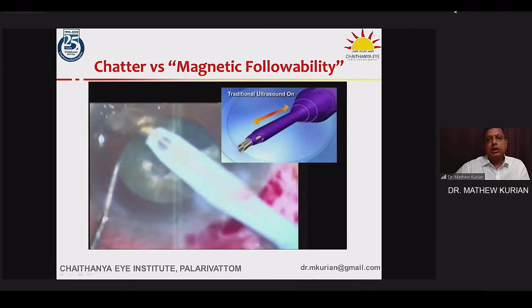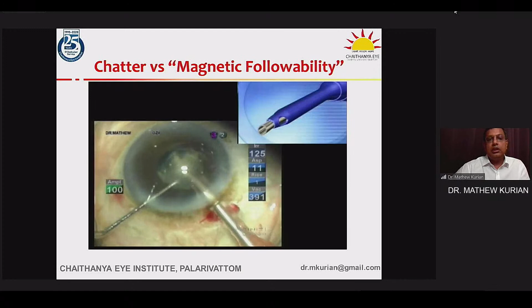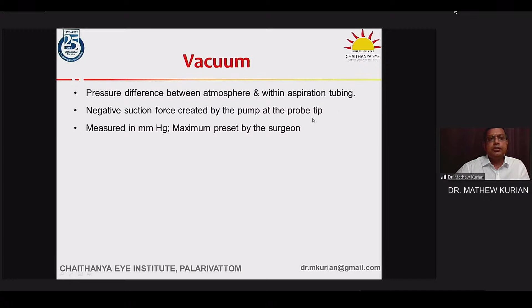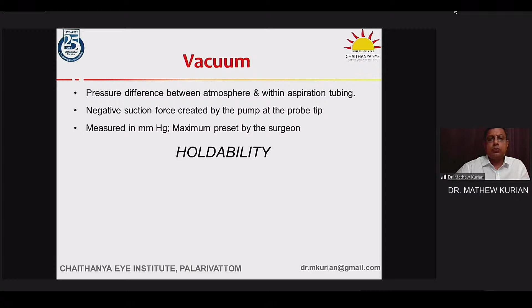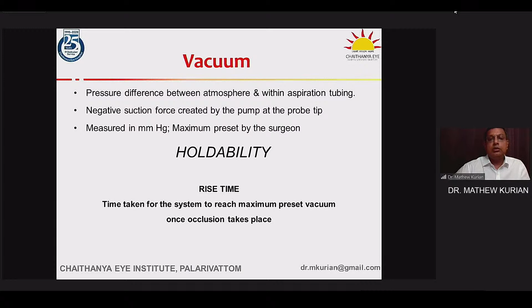And this is more common in the traditional machines with the longitudinal ultrasound, where the fluidics has to work extra hard to bring the tip to the piece. The shearing force used during torsional phaco repels the nucleus fragments much less, and so you have what they like to call, in the marketing portion, magnetic followability. Vacuum is a pressure differential between the atmosphere and within the aspiration tubing. It's a negative suction force created by the pump at the probe tip. You can call it holdability, and the rise time is the speed at which the system, once it is occluded, reaches the preset maximum vacuum, and it can be made faster or slower on both Venturi as well as peristaltic machines in the more modern machines.